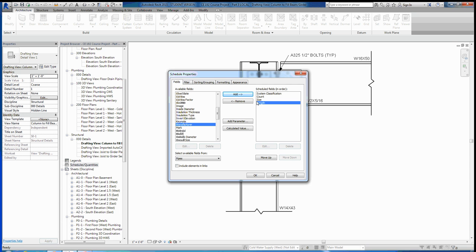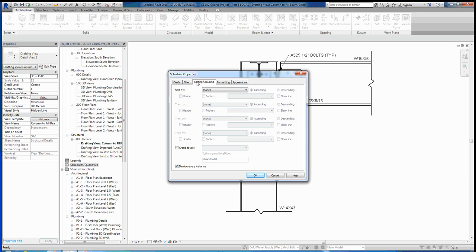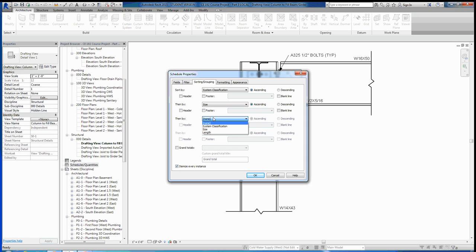Once we've done that, we can look at these other tabs. The filter tab will allow you to filter different things out if you don't want to show a certain type of pipe or something like that, but we're not going to worry about that. Let's go to sorting here. We have to tell Revit how we want these organized, how we want to sort them. The first thing I want to sort it by is by system classification, and we can say we want it to be ascending, which means it's just going to go in alphabetical order. Then after that, I want to sort it by the pipe size, the diameter of the pipe. I want all those to be grouped together in the correct order. And then finally, I want each thing to be filtered by the length. So now you can see we have system classification, size, and length, and all of these are going to be recorded for each pipe segment we have in our model.